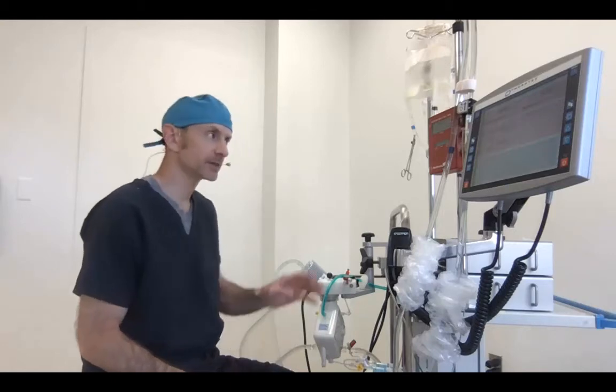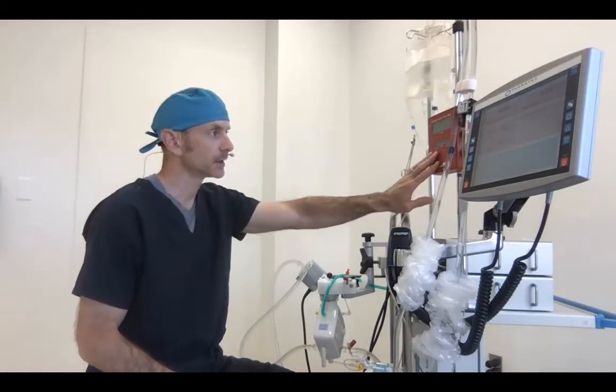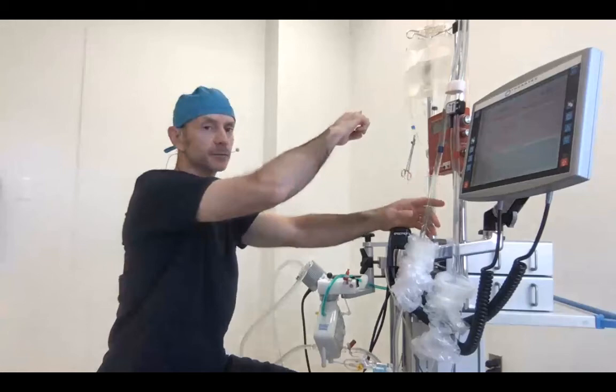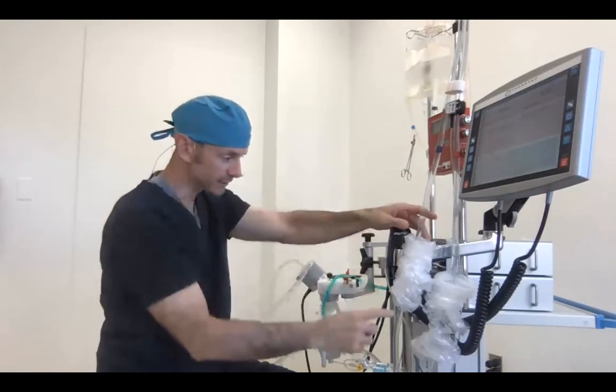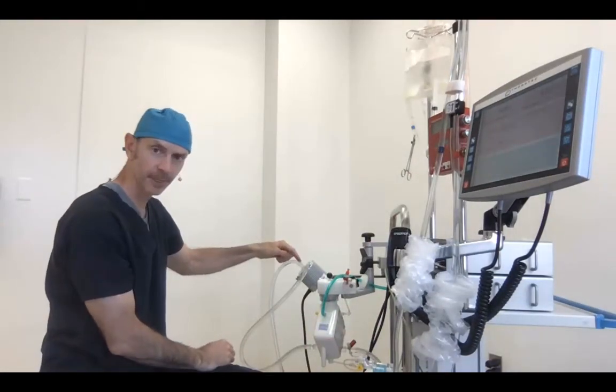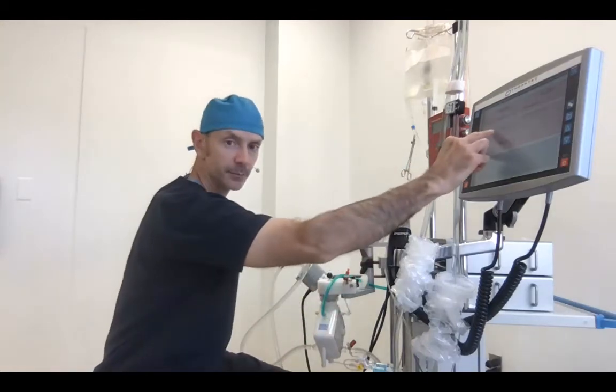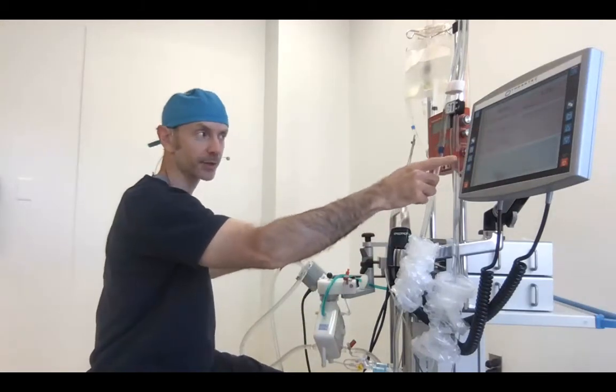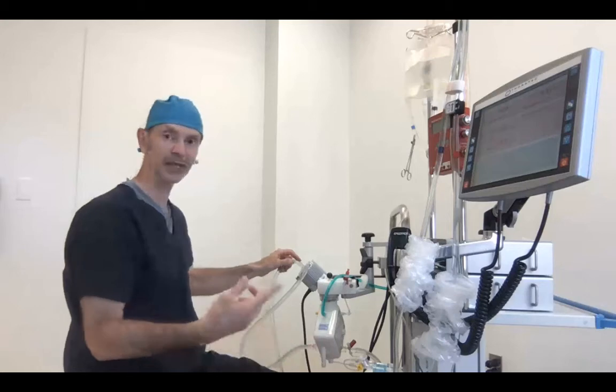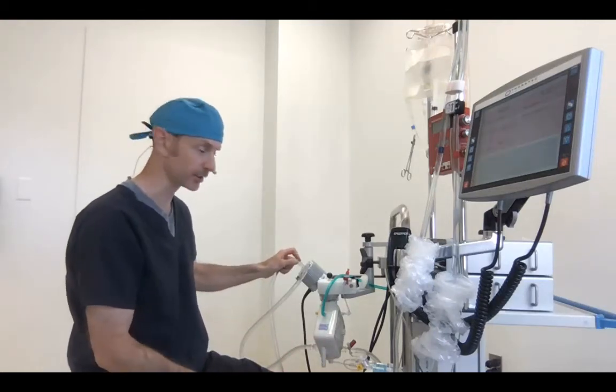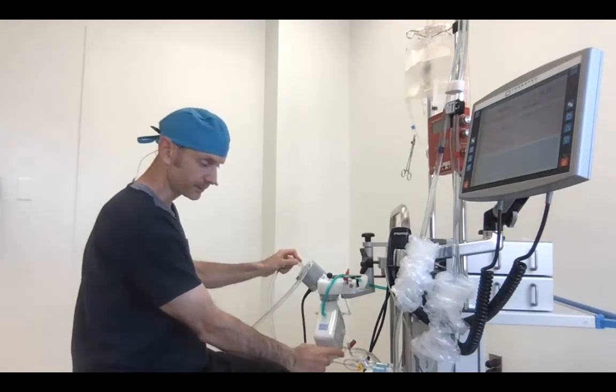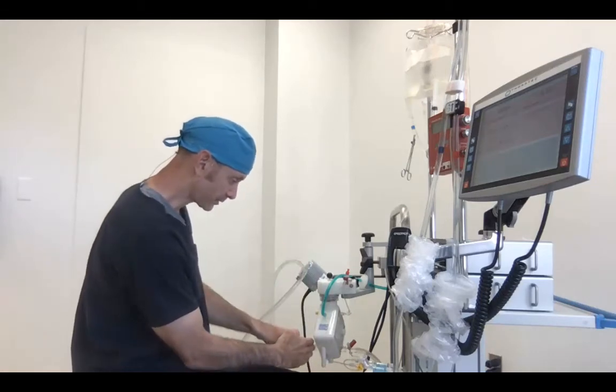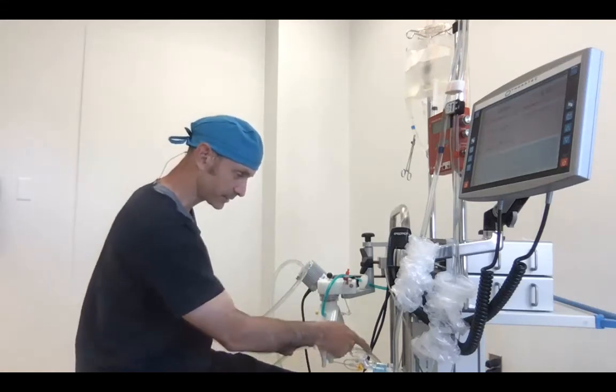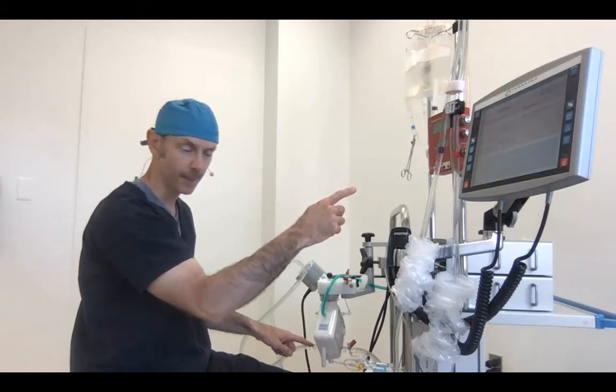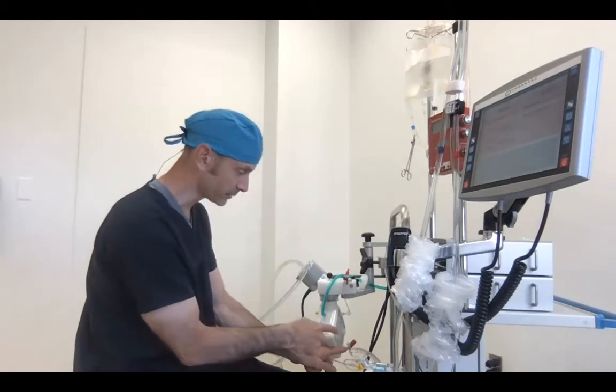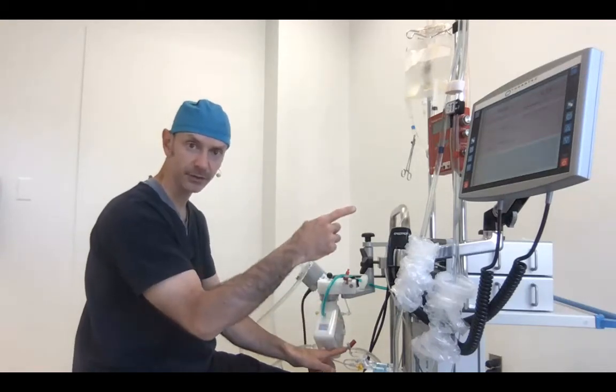Okay, so we've talked about the venous line pressure and how it monitors the venous line from the cannula to the venous line all the way down to the inlet of the pump. We've talked about the arterial line pressures, or the pre-membrane and post-membrane, or P1 and P2, or P-int and P-art if you're looking at the CardioHelp. We've talked about these pressures, and one of them starts here and includes the oxygenator, the arterial line, the cannula, and the patient. And the other one starts here and includes the arterial line, the cannula, and the patient.